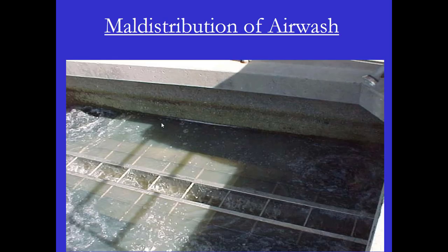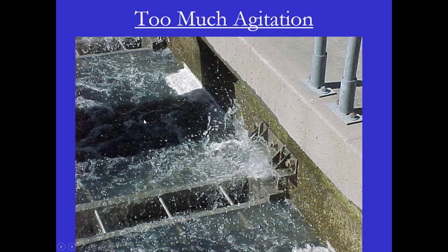If the filter has an air wash system, you also want to carefully watch the air wash. Here you can see there's a lot of agitation here and here, but almost nothing in this area. You would see all this water shooting up during the air wash. This is a problem because in addition to water shooting up, you're also shooting up media, which goes to the trough and is lost, causing a problem with backwash time.